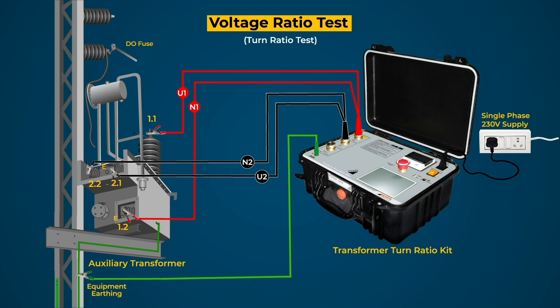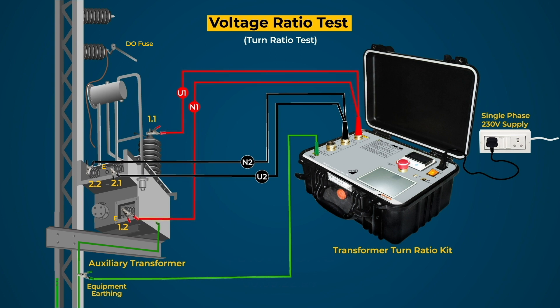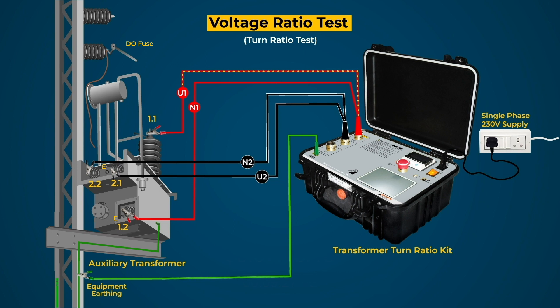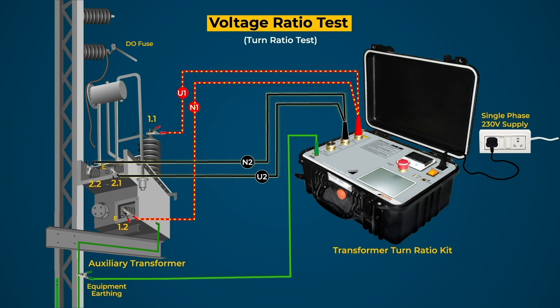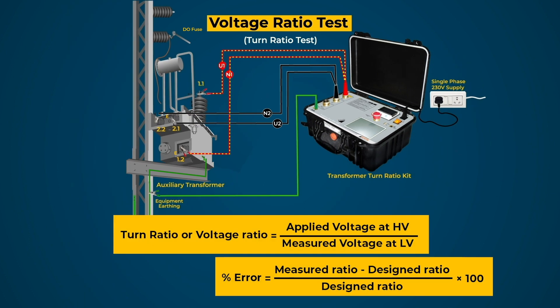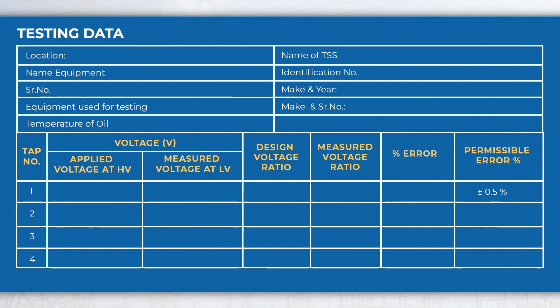Check all the connections and switch on the single-phase AC supply. Now 30 volt AC voltage is injected to HV winding and a voltage is induced in LV winding, which is measured by the test kit. The kit calculates the turn ratio and percentage error. Conduct the test for all the taps of AT. Testing data may be recorded in this format for further investigation and future reference.